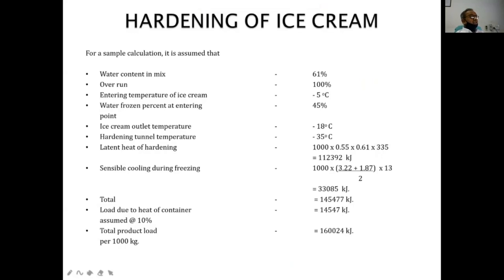As I explained to you earlier, ice cream contains 35% to 40% solids and the remaining is water. In this case, I assume it contains 61% water, and the remaining 39% is total solids. Total solids means it contains fat, solids-not-fat, sugar, stabilizer, and emulsifier. That is generally 35 to 40% in ice cream. We can assume the ice cream has 100% overrun. Why do we assume it? Because in refrigeration load we are concerned not with the volume of the ice cream but with the mass of the ice cream, and to calculate that mass we should know the overrun of the ice cream.